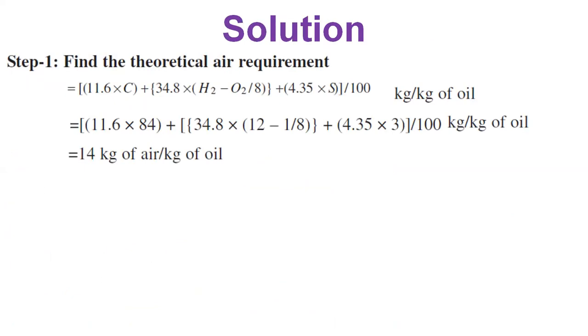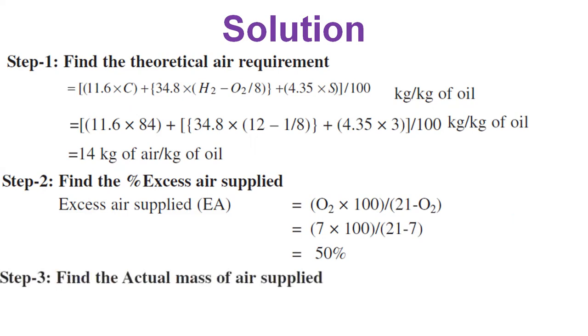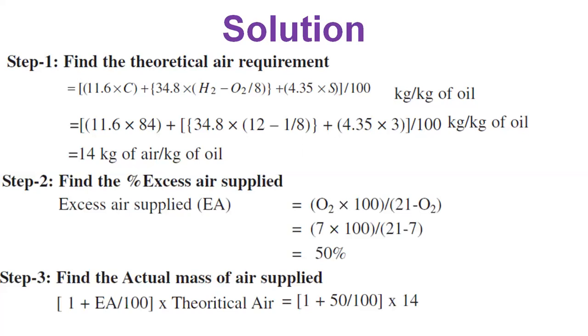Step 2: excess air supplied = (7 × 100) / (21 − 7) = 50%. Step 3: actual mass of air supplied = (1 + 50/100) × 14 = 1.5 × 14 = 21 kg of air per kg of oil. We then proceed to estimate all other losses.